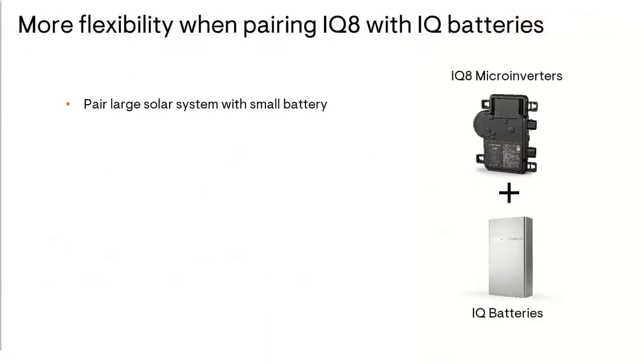Now that we're introducing a battery into the configuration, let's review one of the key benefits of the new IQ8. Since the IQ8 can respond extremely quickly to changes in power demand to keep the microgrid stable, the strict 1.5:1 ratio of solar AC power to battery AC power with previous generations no longer applies with the IQ8.